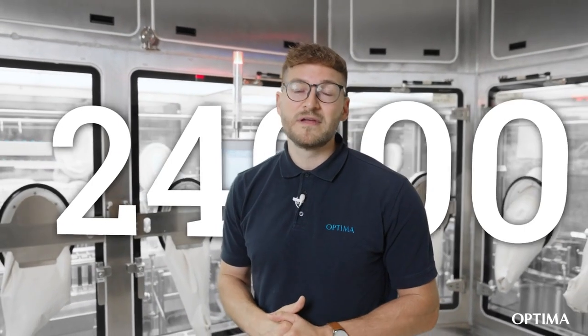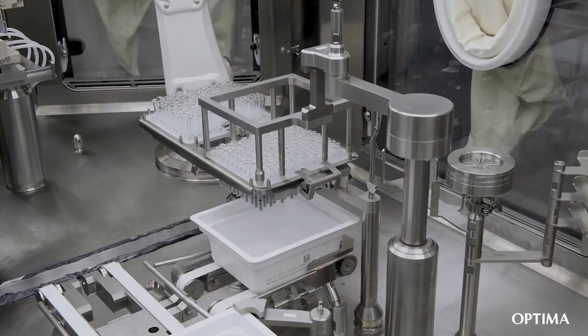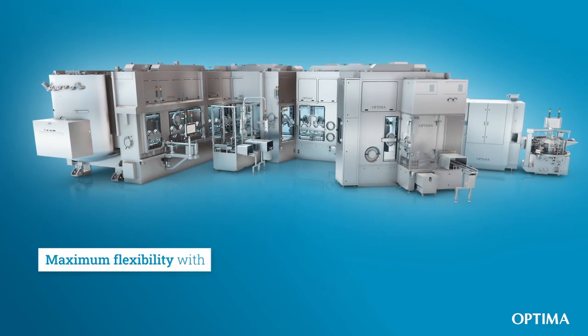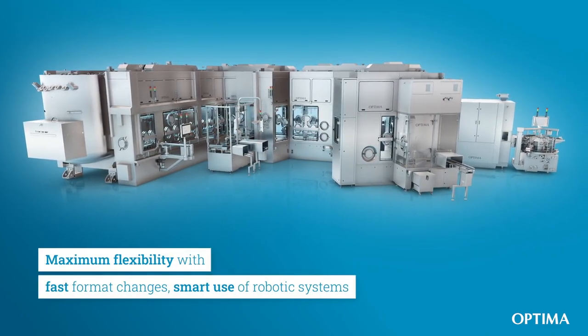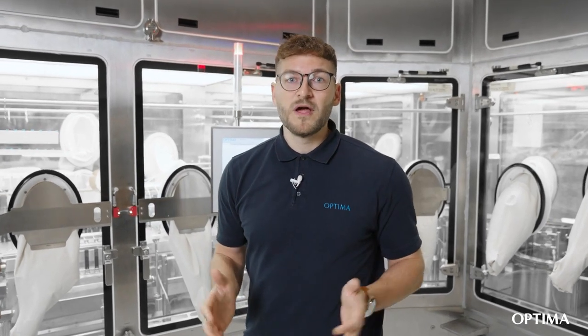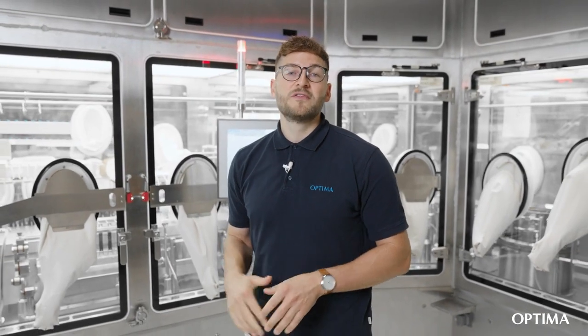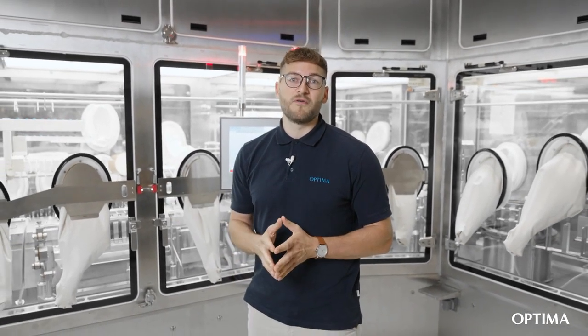As the name says, the Multi-Use runs up to 24,000 per hour for syringes, cartridges and vials. The new Multi-Use combines all the needed features like product saving, restoppering and 100% IPC. On the line we have the new magnetic transport which comes with state-of-the-art robotic technologies to reduce also the interventions of operators.